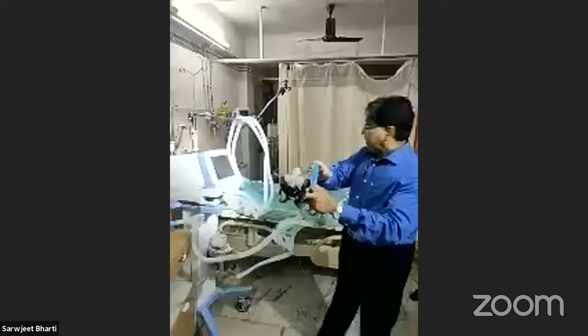And the best way to use this machine is you have the BiPAP machine, that is the outlet. You attach it to one humidification filter, an HME filter, and to improve the oxygenation, to give extra oxygen, you attach the wall outlet through a pipe to the HME filter and connect it like this to the patient. And then using the Venturi phenomenon, oxygen will be drawn from the wall outlet and the patient will get enhanced oxygen supply.